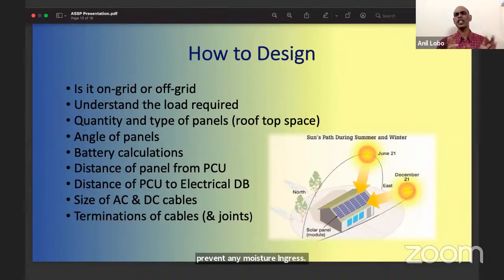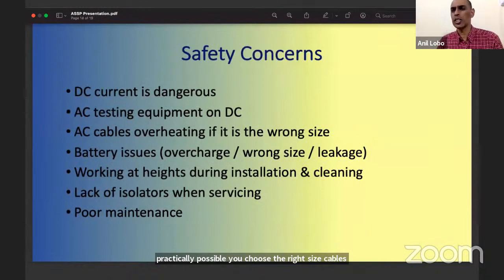So these are the factors that you have to look into while designing. You have to sit with the system integrator to ensure that your batteries, your solar panels, and your power conditioning units are sized properly. If these things are not sized properly, you're in trouble. Your angle of the panel has to be proper, and the distance of the panel to the PCU has to be as close as practically possible. You choose the right size cables and you terminate them efficiently. And that takes us to some of the safety concerns.